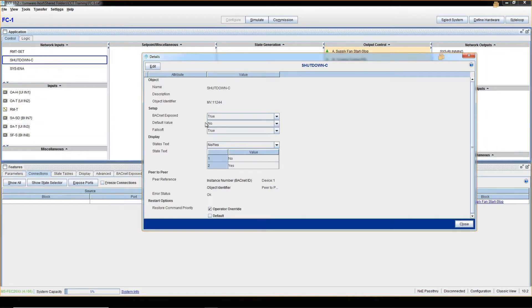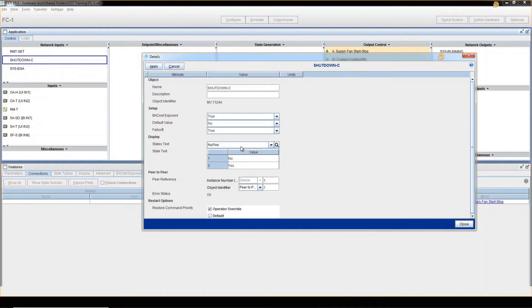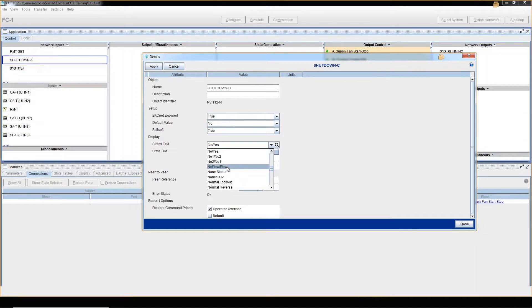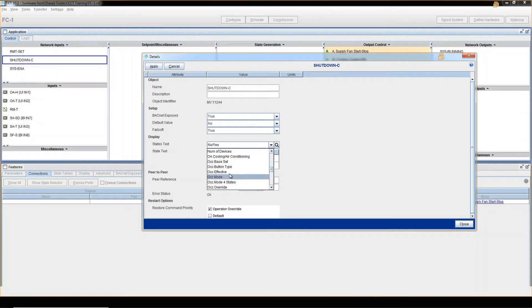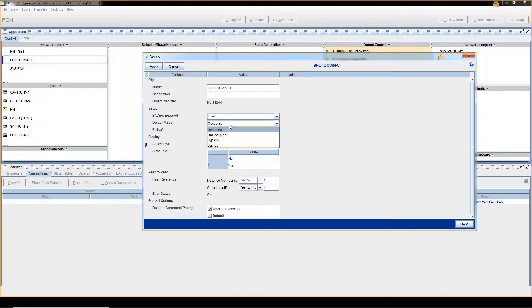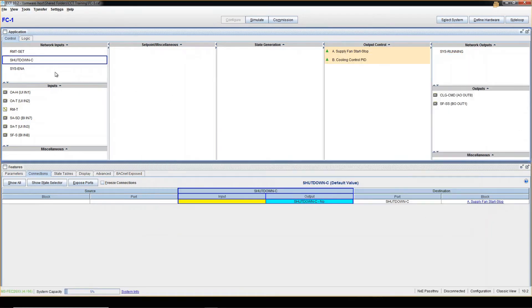We have a default value and state text which are the units: No/Yes. So this is an Enum — Enumerator. This is not false/true, it's No/Yes. It could be Normal/Reverse, No/Non-Status, No Flow/Flow, or multiple values like Normal/Short/Open. If you go to a network input like occupancy effective and check the default value, you can tell it's a four-state value: Occupied, Unoccupied, Bypass, and Standby. So that's an Enumerator — an Enum.